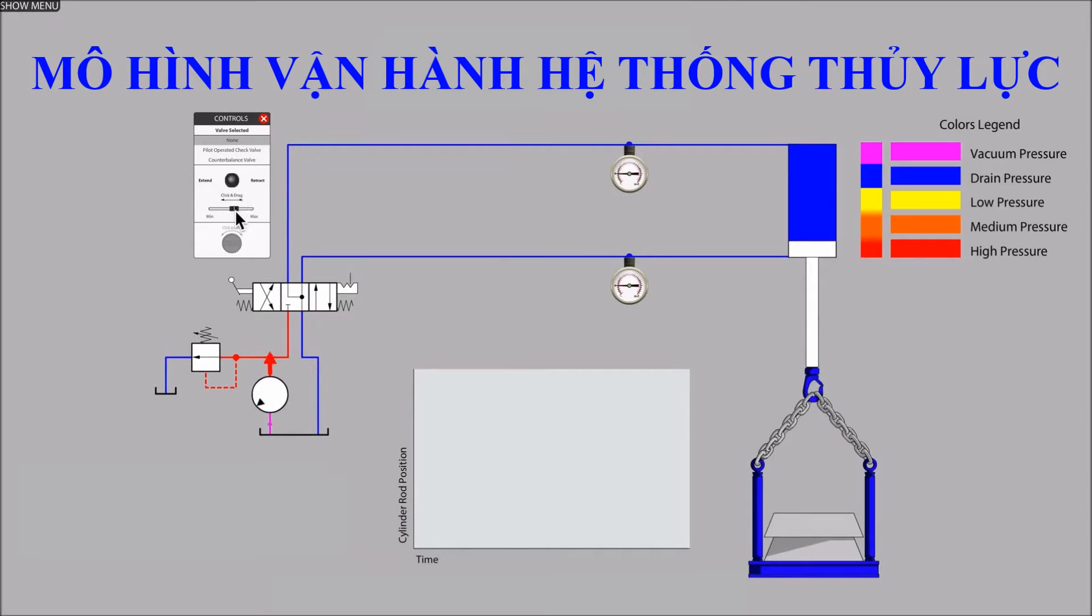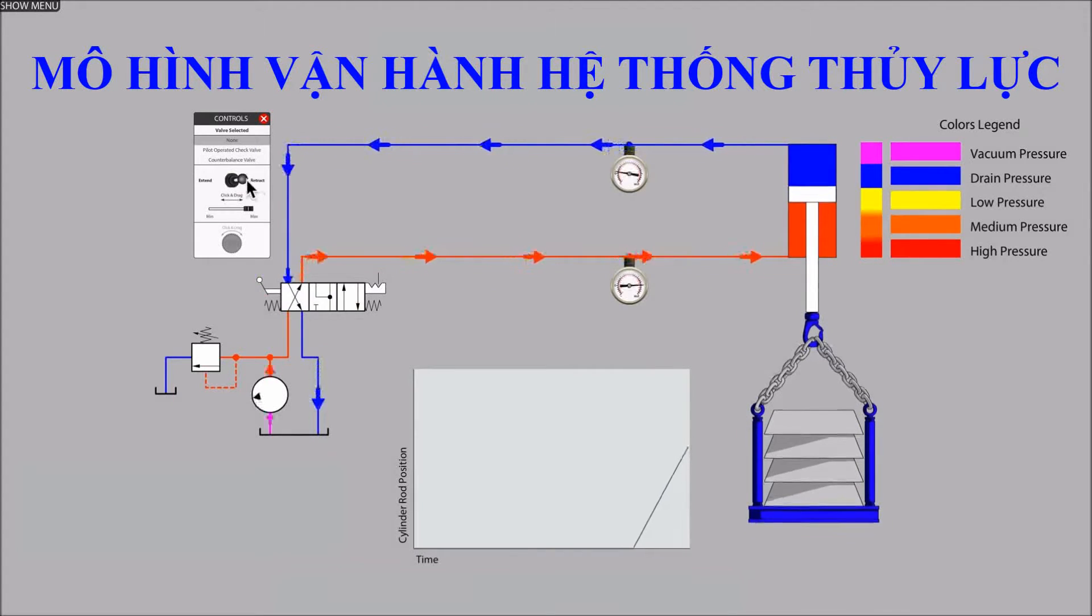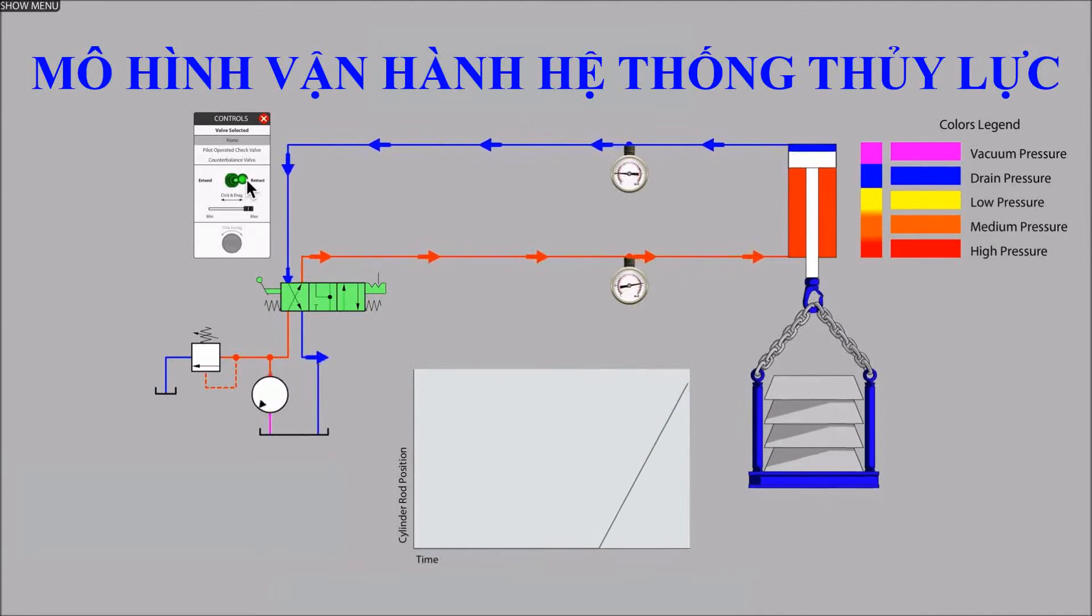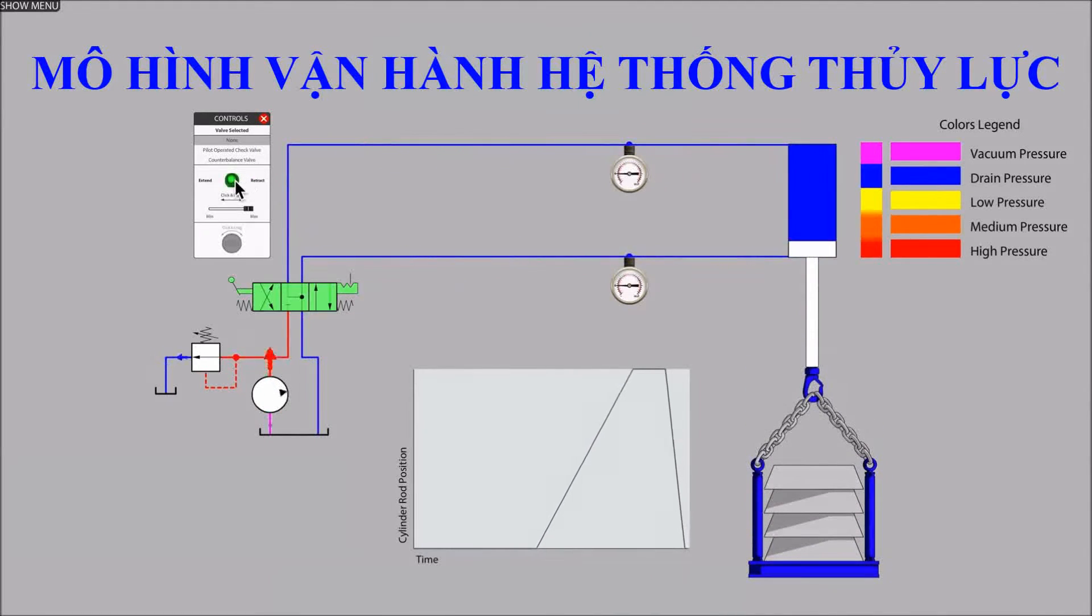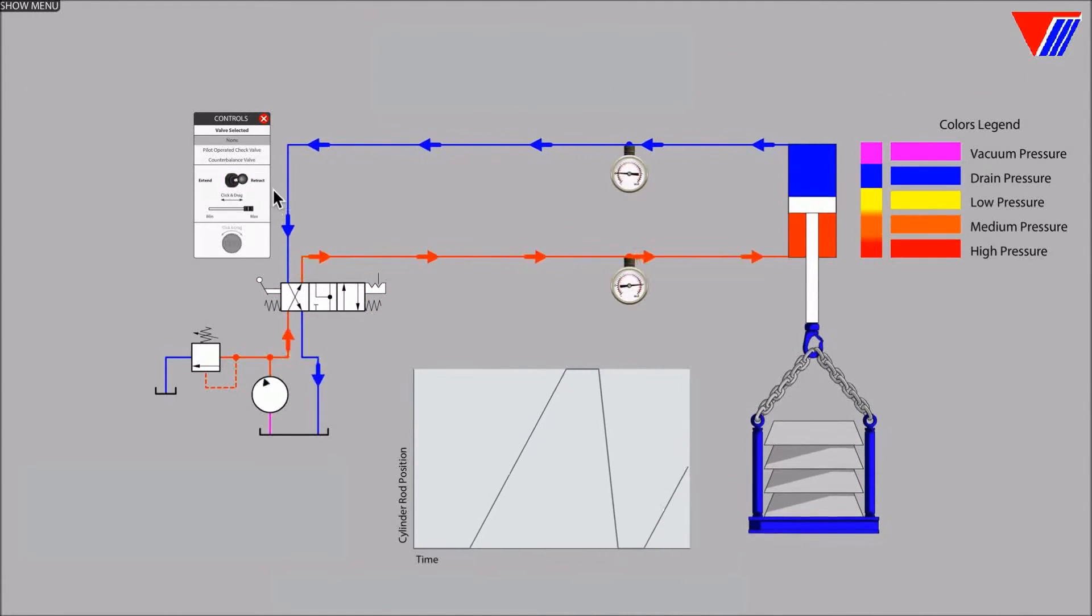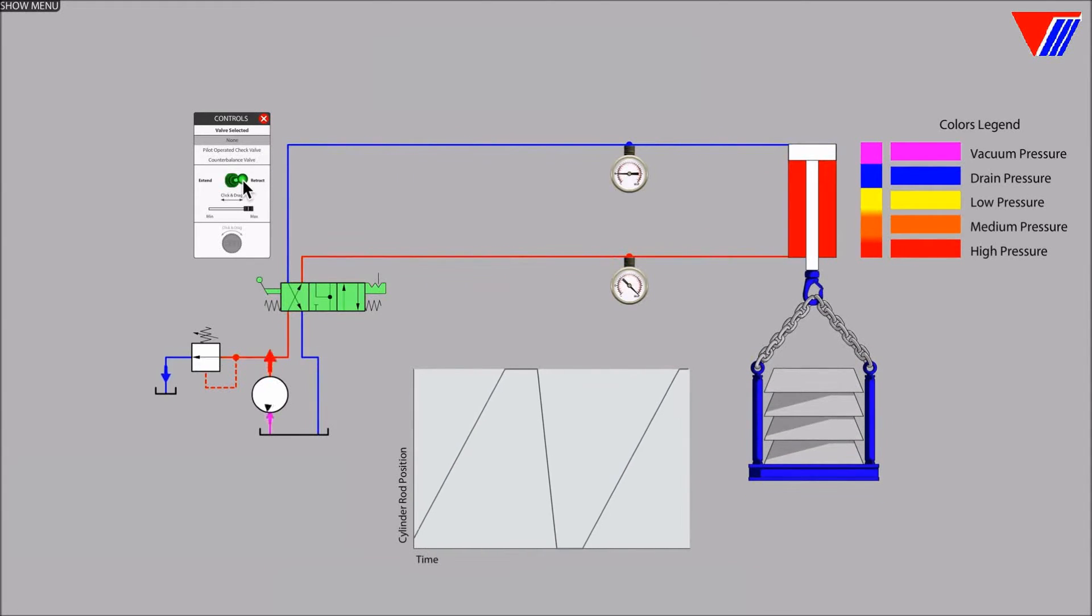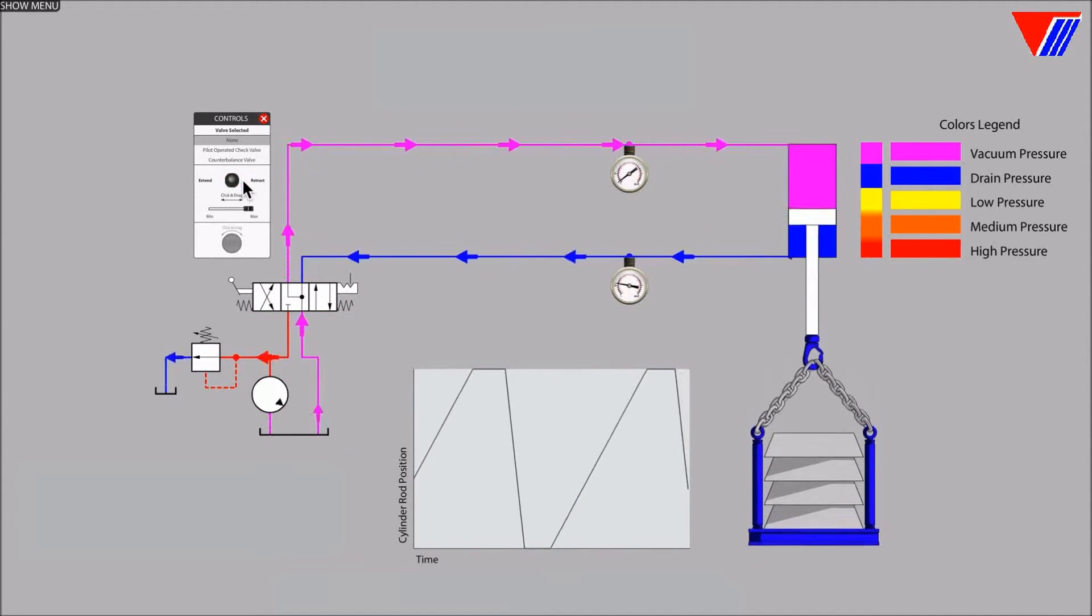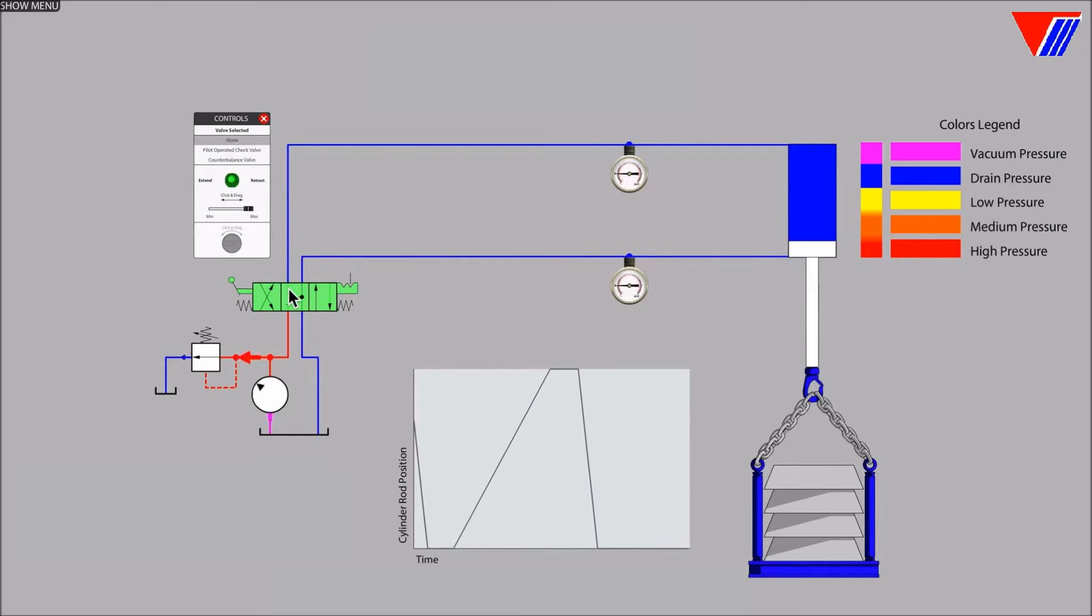A vertically loaded hydraulic cylinder will require a lock valve of some sort to hold the cylinder at a mid-stroke position or perhaps a counterbalance valve to prevent runaways while lowering a heavy load. A directional control valve is seldom relied upon for these functions.